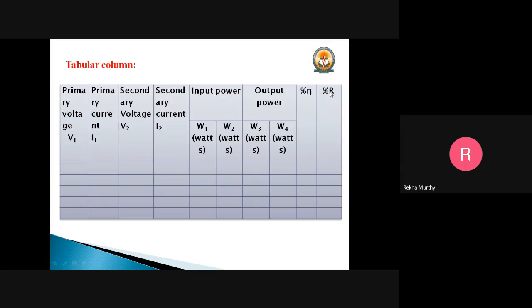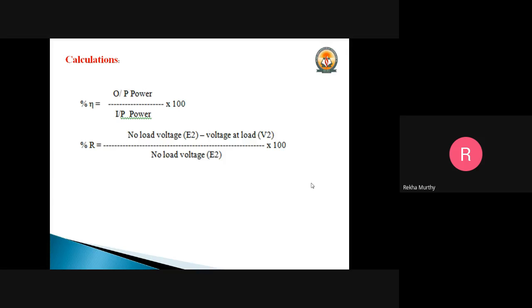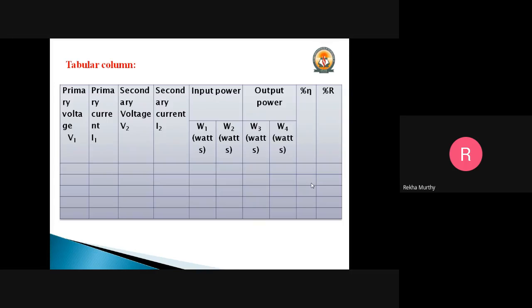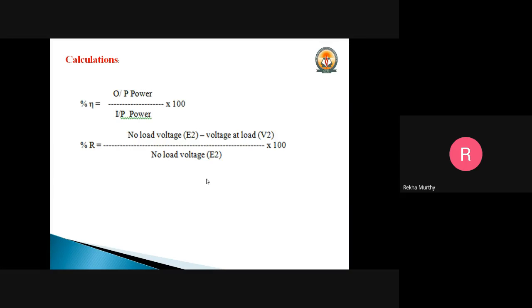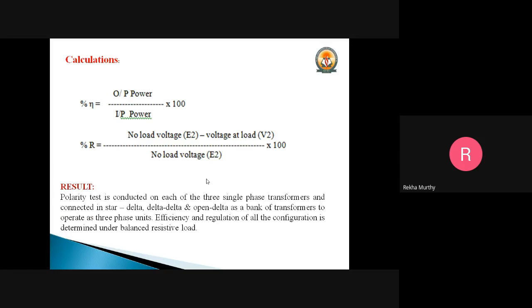As per regulation, the formula is no load voltage minus full load voltage divided by no load voltage. The first reading you get is the no load voltage, and from the second reading onwards it is all loaded voltage. So you need to take the difference between the first reading and each successive reading, divided by the no load voltage from the first column. Like that, you need to find the regulation for all the steps with different loads.